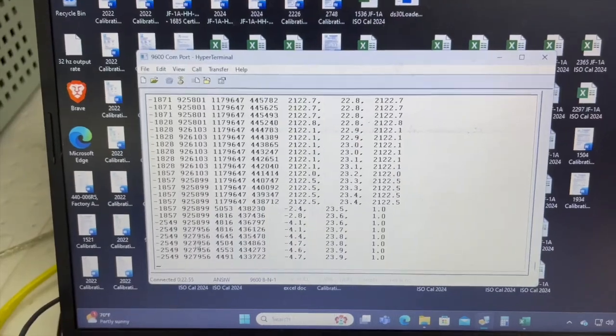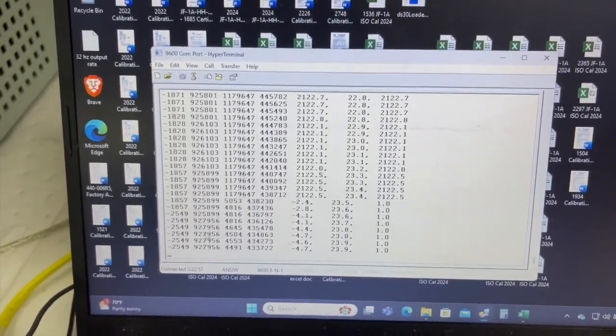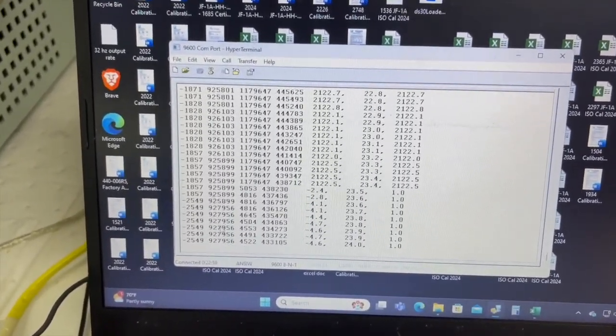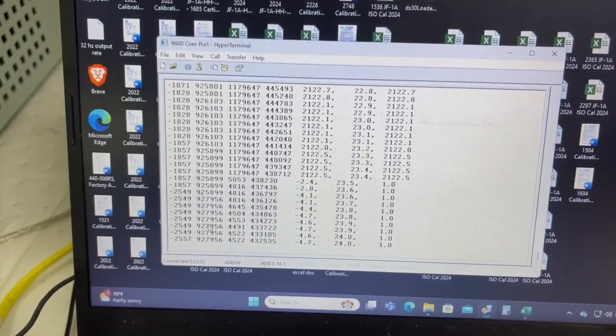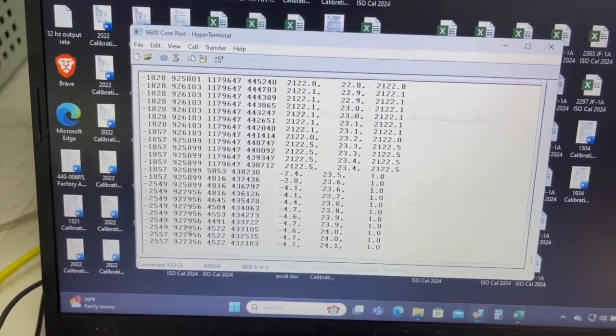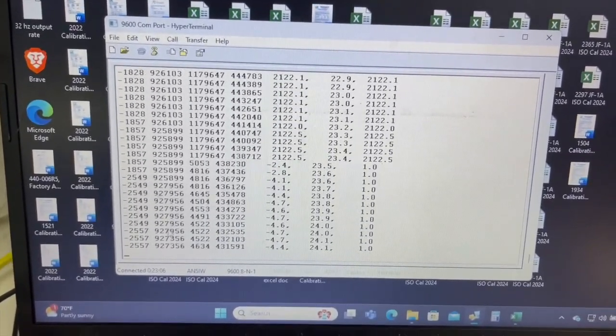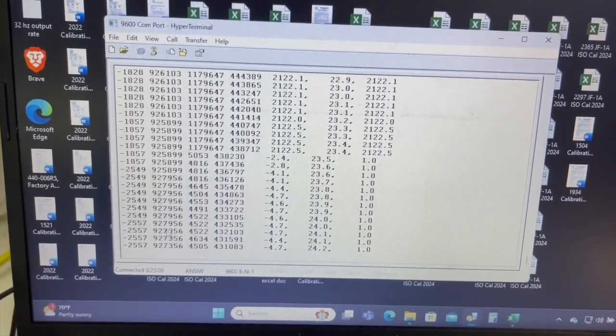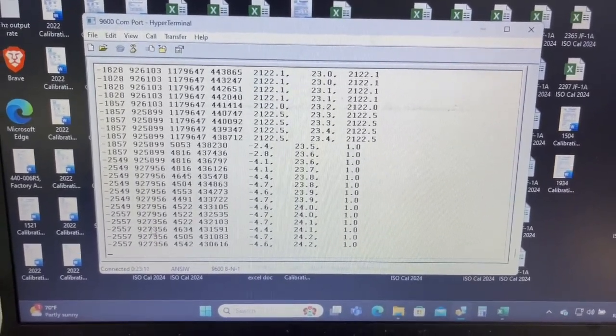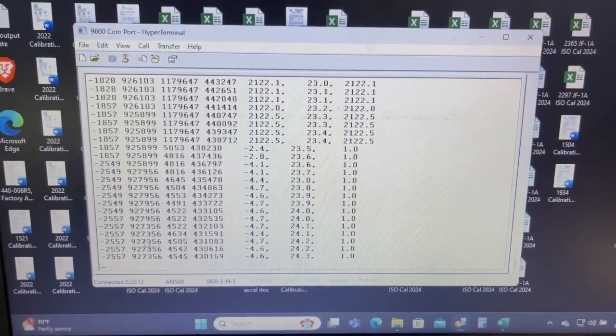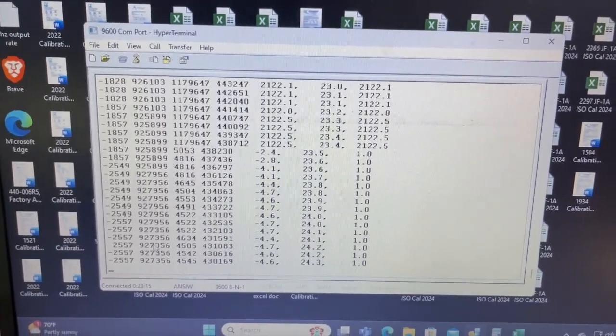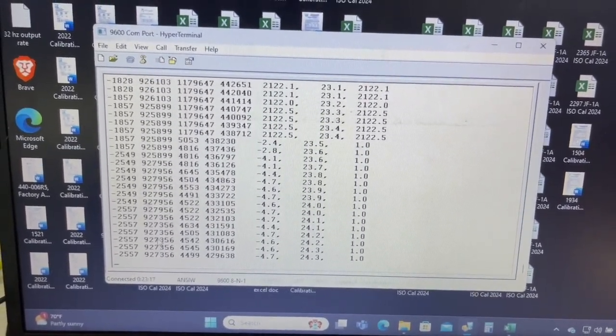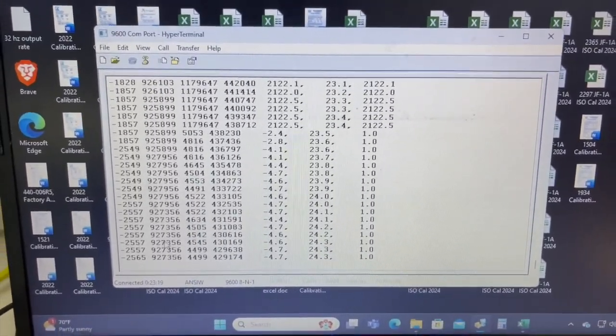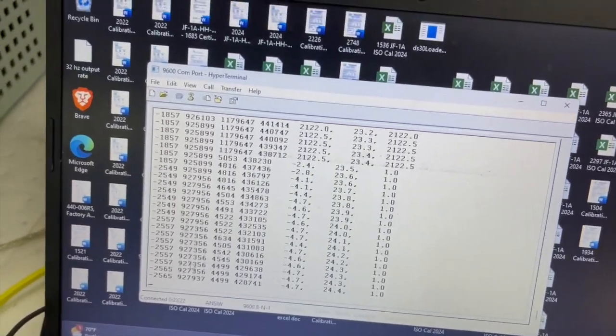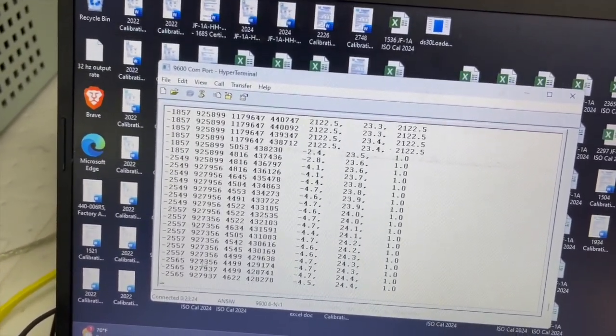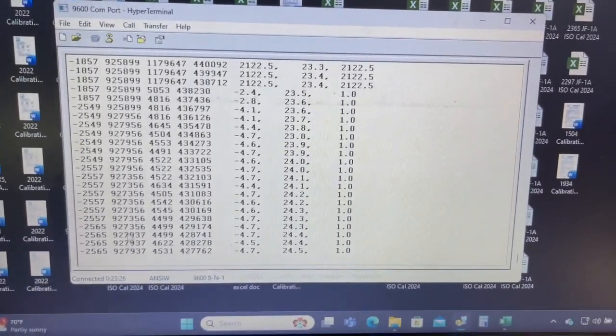So if you're ever wondering if the sensor is working or not, say, is the sensor working at all? You can always pull it out of the line and do this test with your finger and in air and see if the sensor will drop to 0 or if the sensor will go up to full scale with your finger across. That's always a good sign if the sensor is working or not. So as long as that works, you now have passed the functional verification segment.